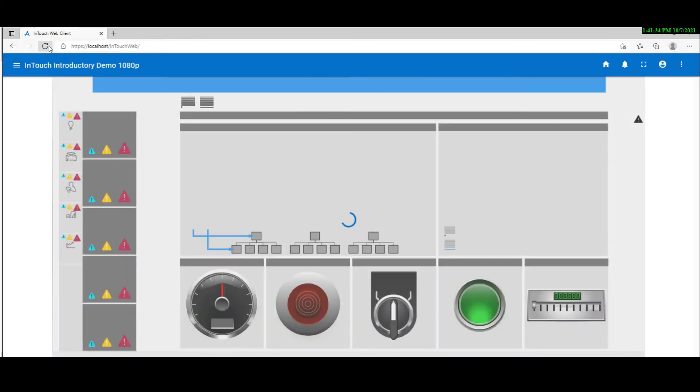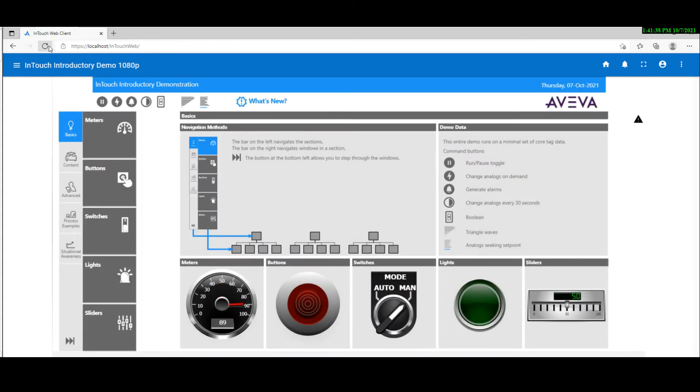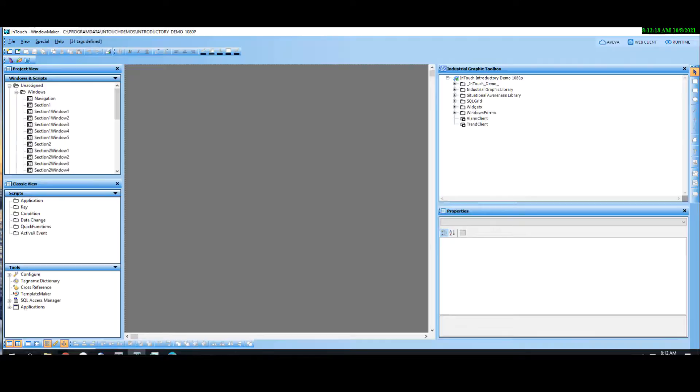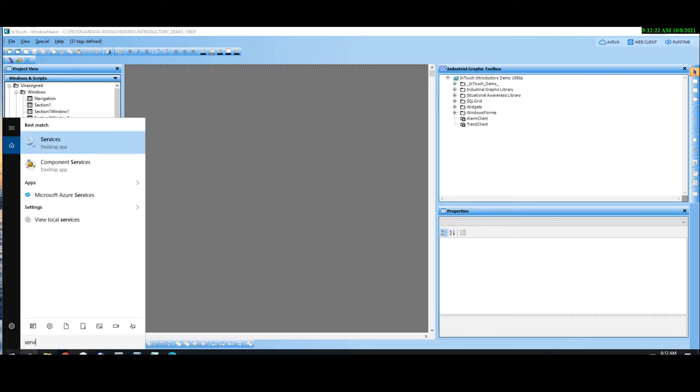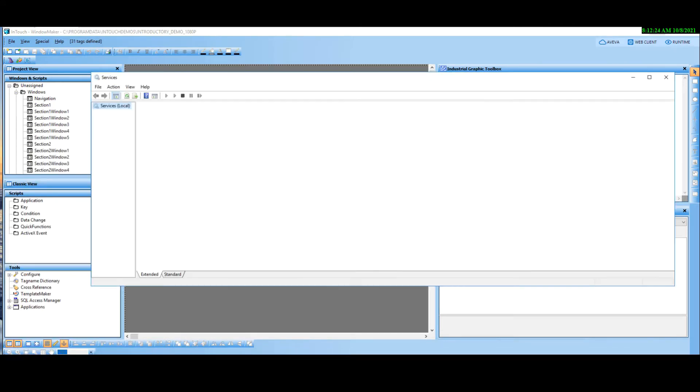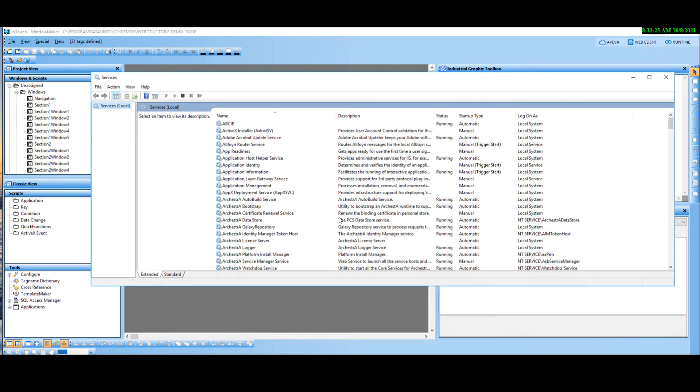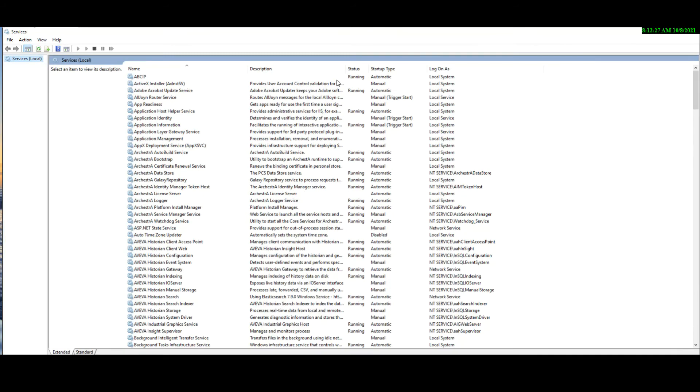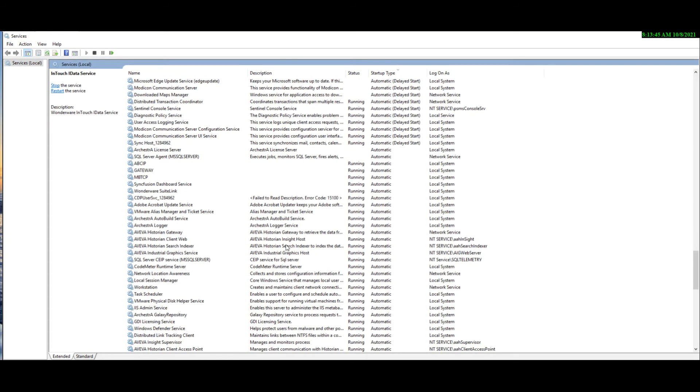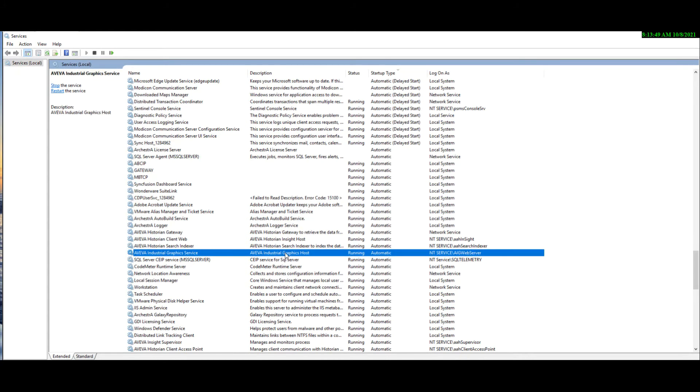And then it will start Window Viewer, which provides data for the Web Client animation. The AVEVA InTouch Web Client utilizes two services. The first one is Hosting Service, which is the AVEVA Industrial Graphics Service. The second one is the InTouch iData Service. Both are automatically installed with InTouch, no need for any configuration installation or any setting up work.